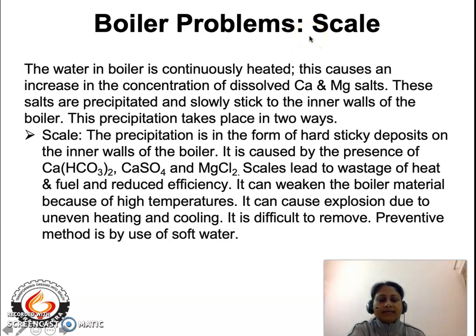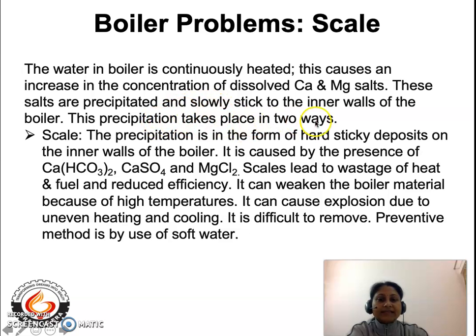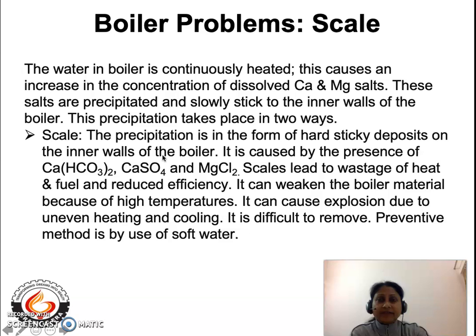The first problem is scale and sludge formation. When water is continuously heated in a boiler, the water converts to steam, but the dissolved salts do not. The salts precipitate out and stick to the inner walls of the boiler. Scales are hard and sticky precipitates deposited on the inner walls, and they are very difficult to remove.